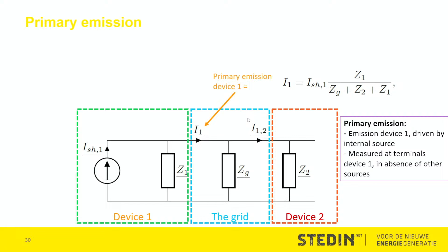In practice, there will also be a grid connected to it, and this primary emission might be affected by other devices connected to the network. In this example, we have one device with a certain emission, I superharmonic 1, a certain impedance, so this is the simple Norton representation of the device, the network, and another device which in this case is just an impedance. If you look at the primary emission of device 1 measured at this point, it is not just this value anymore.